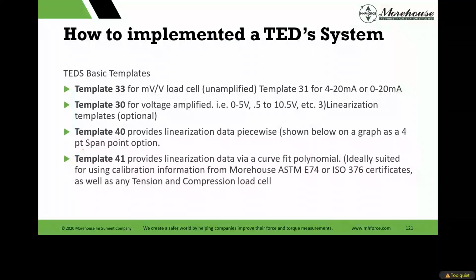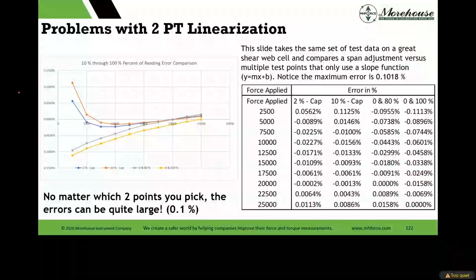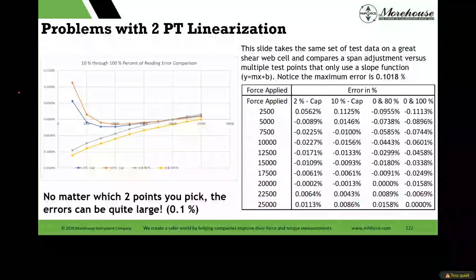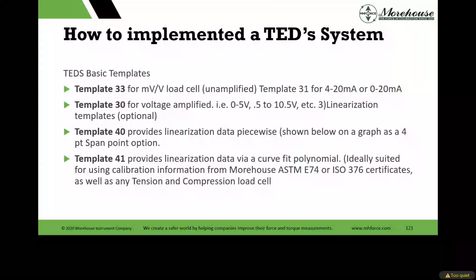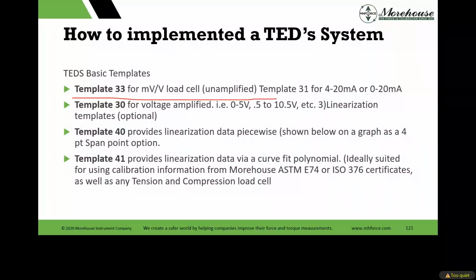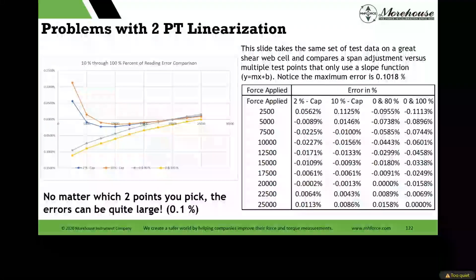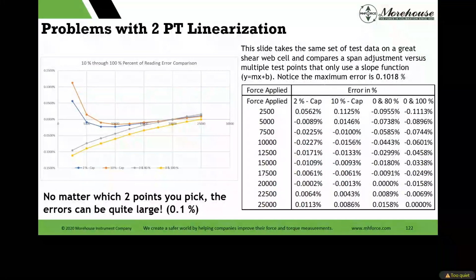So what does all this mean? This is already starting to become confusing, and even though I've taught this in-house, I've taught it to other people, and I've written papers on it, it's still a word salad to try to explain. So the best I can do is say, we're overloaded with templates, and template 33 is what we want to remember for right now. Most meters that say TEDS will be TEDS compliant with template 33, which means you can store information on the load cell, such as the serial number, the capacity, and a 2-point span.